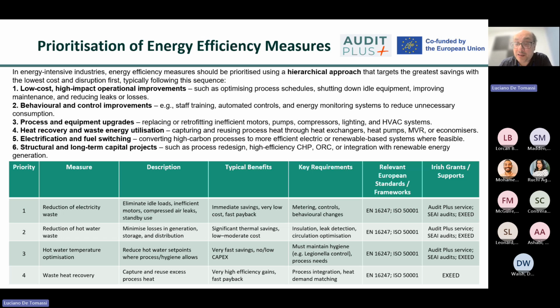Once operational efficiencies have been maximized, organizations should evaluate opportunities to improve the efficiency of core equipment and process systems. Examples include replacement or retrofit of inefficient motors, pumps, compressors, fans, and HVAC systems, installation of variable speed drives and advanced process controls, upgrading insulation, pipework, and heat distribution systems, and modernization of heating equipment to improve thermal efficiency.